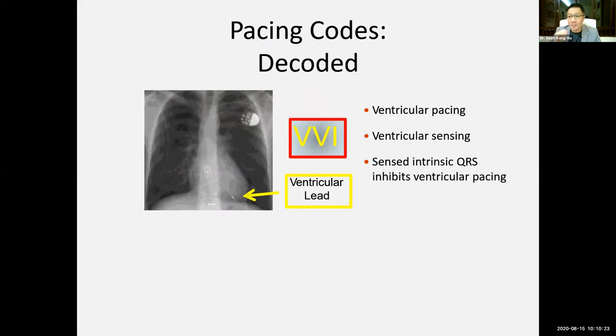Let's go to the most basic of all the pacemaking codes that we can have. We all started our careers with this, understanding VVI. Now V, the first alphabet, is which chamber has been paced. In this case it's the ventricle, so it's a single lead system, single chamber system going to the ventricle. It paces in the ventricle and it senses in the ventricle. Now, what would I do as a pacemaker if I sense an intrinsic cardiac electrical activity? I inhibit myself. I means I don't pace, I inhibit myself. Now this is very easy to understand.